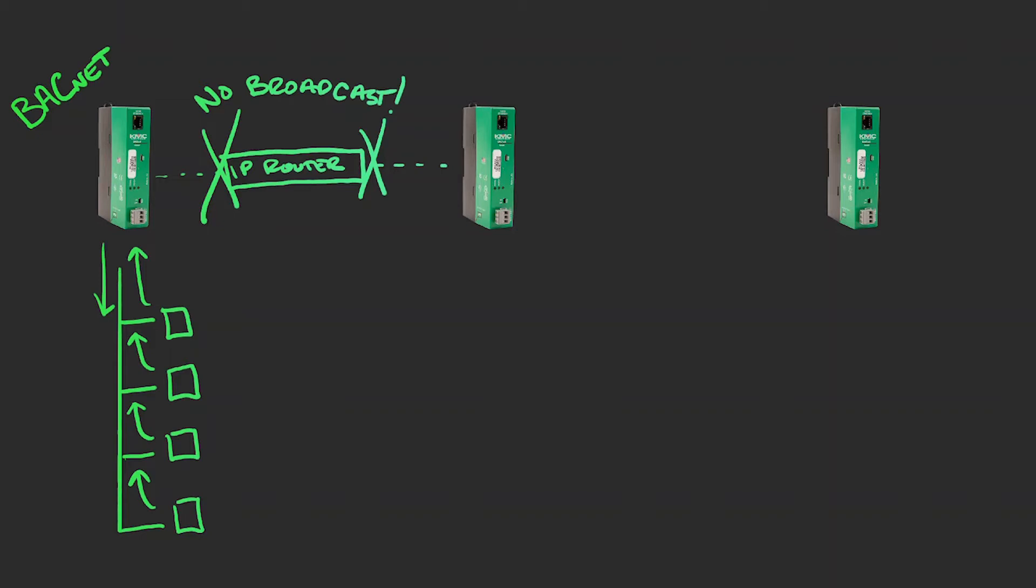Though BACnet routers can forward broadcast messages, the IP routers do not. This lack of broadcast forwarding by IP routers prevents the BACnet routers and devices from discovering routers and devices on other BACnet networks.